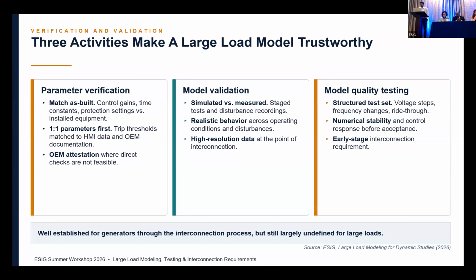Then model quality testing - this has been done quite a bit on the generation side, and we're starting to see similar requirements on the large load side. Those are your regular voltage step-ups, step-downs, frequency changes, ride-through settings, and phase shift - so you start testing all of those for each model.